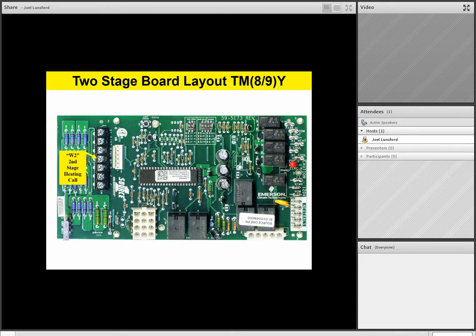R is our 24 volt hot, just like we had before. G is our fan on call, very conventional. And C is our 24 volt common. Now as we move around the board, let's go ahead and talk about some of the key features of this board as well. Our last error button is going to operate just like we had before on our previous slide and our previous single stage board. You can depress that last error button to retrieve flash codes off the board. If you hold that button down about 10 to 15 seconds, it will also clear the memory.